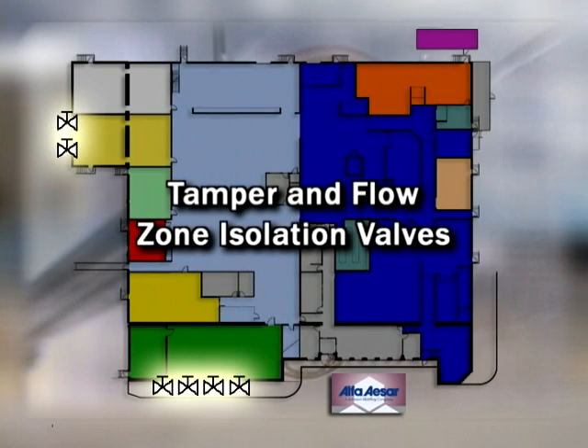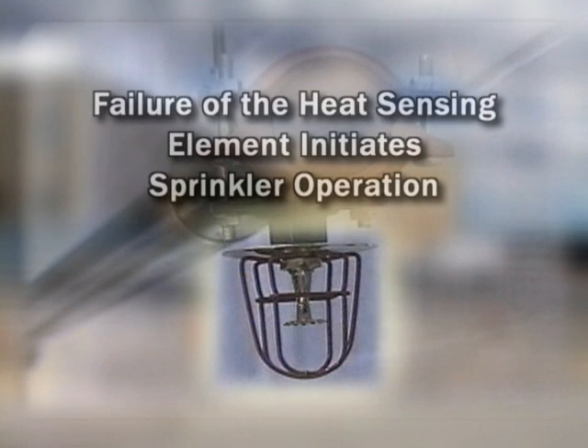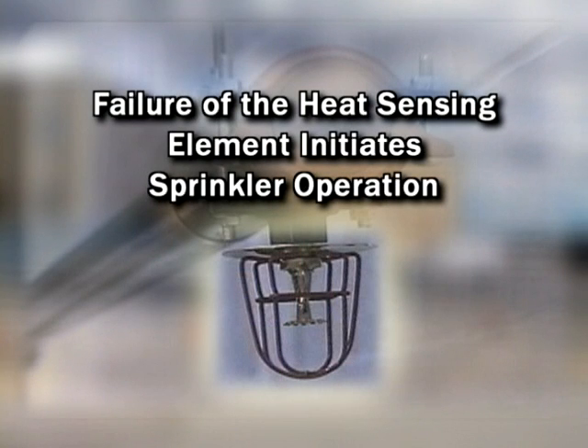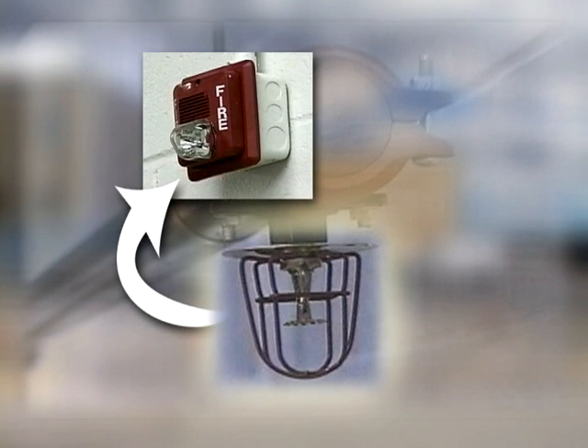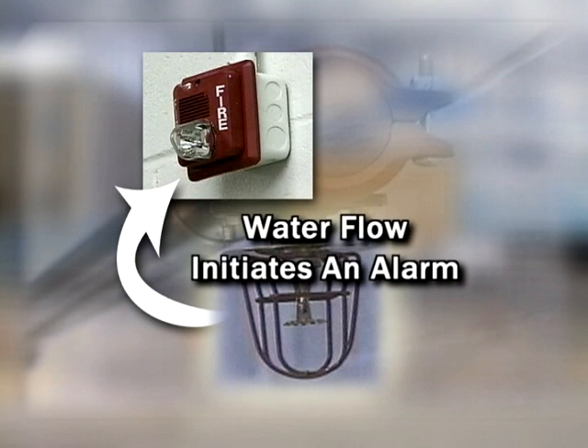Tamper and flow valves are located in or adjacent to each of the areas served by the wet pipe sprinkler system. In the specialized storage rooms, there are isolation valves for the overhead sprinklers. Failure of the heat sensing element at any sprinkler head will result in immediate sprinkler operation in the affected area. Water flow within an individual zone will initiate a fire alarm via the fire detection and alarm system.